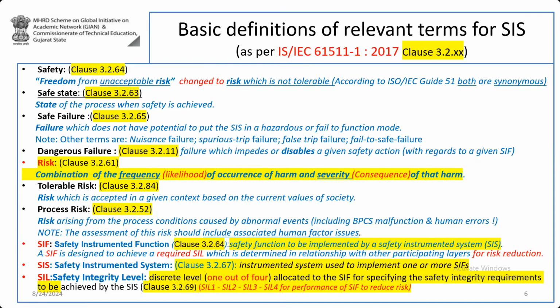Okay, so other terms for the safe failure are nuisance failure. They are known as a spurious trip failure or false trip failure or fail to safe failure. There are various terms used for the same failure. These are as per the clauses, as per the standard. I have not added any words or removed any words from that. And most important now is the dangerous failure.